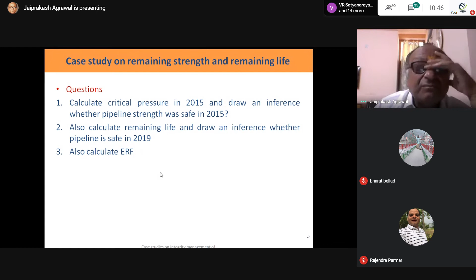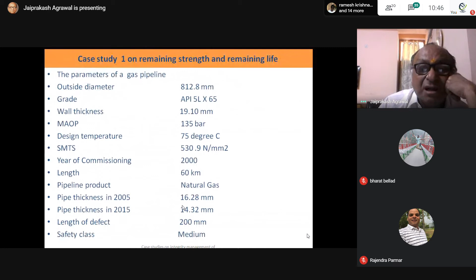See now how I will move that. Corrosion growth rate as per API 570, this is the formula. 19.10 is the original thickness and 14.32 is for 2015. We are taking 2015. So 14.32, 15 years. So 4.78 by 15, that is 0.31 mm per year. If you convert it into mils per year, it is 12.2 mils per year.